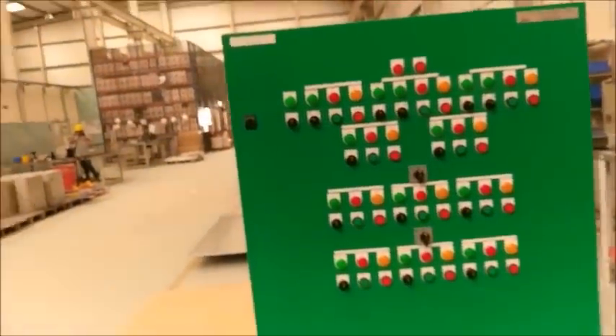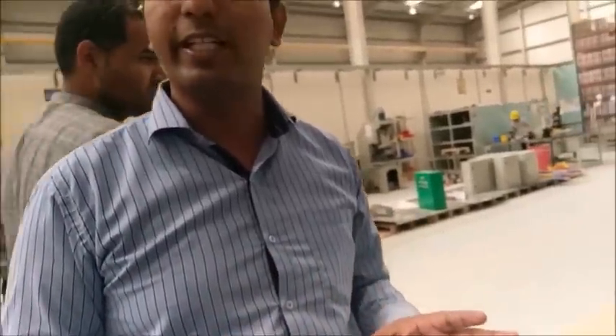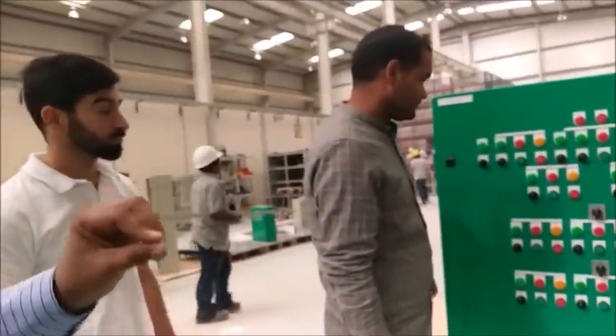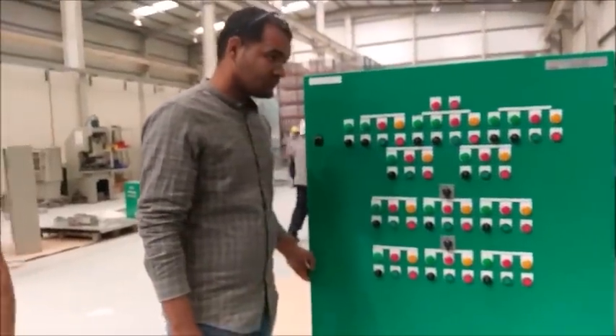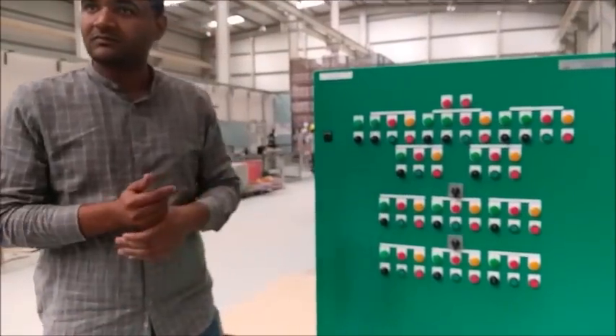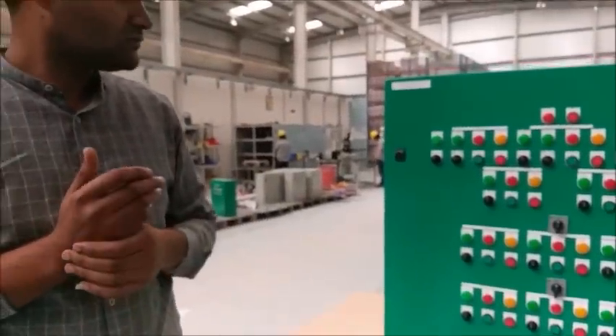We know the technical reason: this is going in a water treatment plant, specifically where there is a lot of corrosion. There is a standard that if there is too much water or a corrosive environment, a green panel will not corrode as early. If I give this color, RAL 7035, in a very dusty area, it will get dirty very soon. The green one will not get dirty soon. So this panel is recommended by Ashghal for their plants, because it will not get dusty as soon as possible.